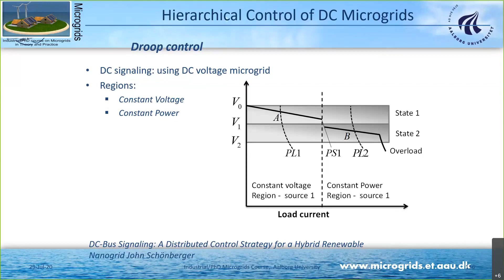If, for instance, the voltage is going very high, it may mean my generation is too big. It's the same with AC power systems and frequency: if the frequency increases, I know I have too much generation. In a DC microgrid, I see exactly the same phenomenon. This is what we call voltage signaling.